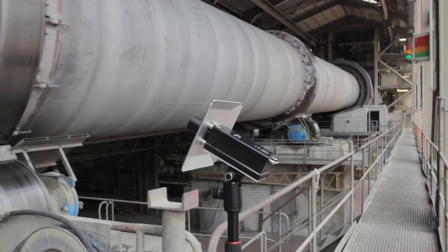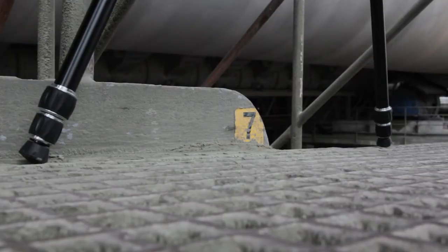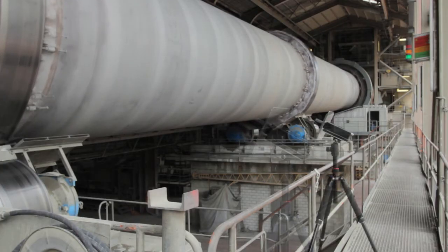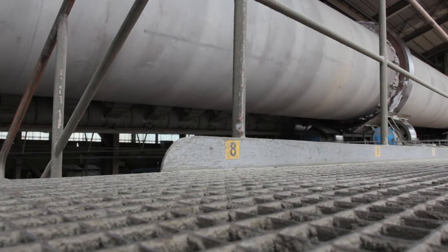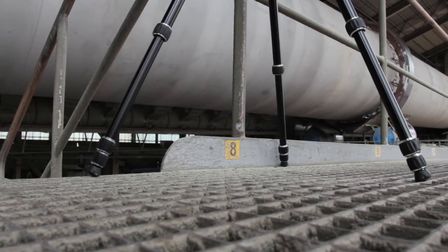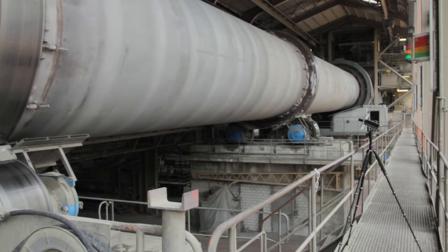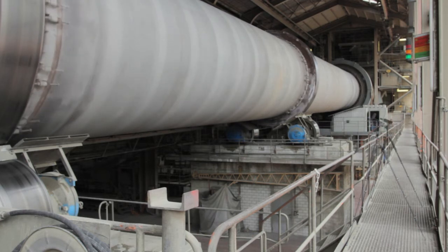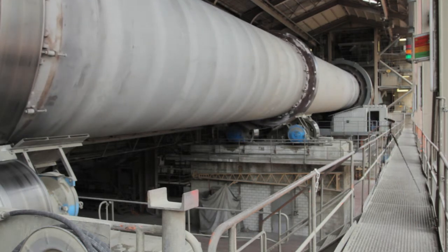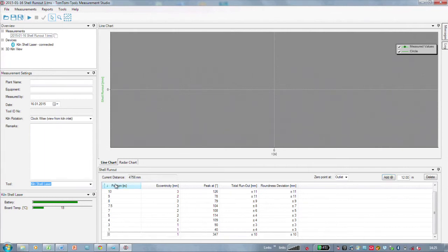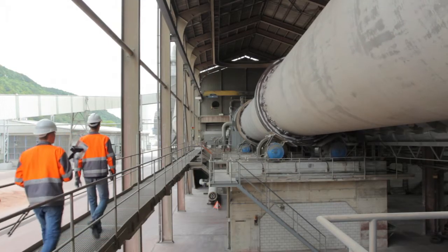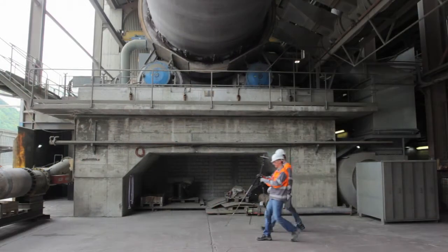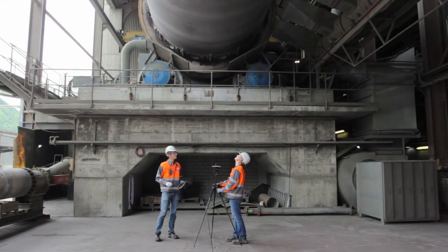To avoid confusion and to work efficiently, it is recommended to have a permanent meter marking either directly on the kiln shell or next to the kiln. The distances between the different readings can be adjusted independently to the access and to the requirements. A typical pattern would be every 1 or 2 meters, in areas of strong deformation every half meter. The order and the window size can be adjusted to keep an easy overview of the collected data. If there is no walkway along the kiln or the measurement is disturbed by excessive heat or sunlight, the laser can be placed below the kiln as well.